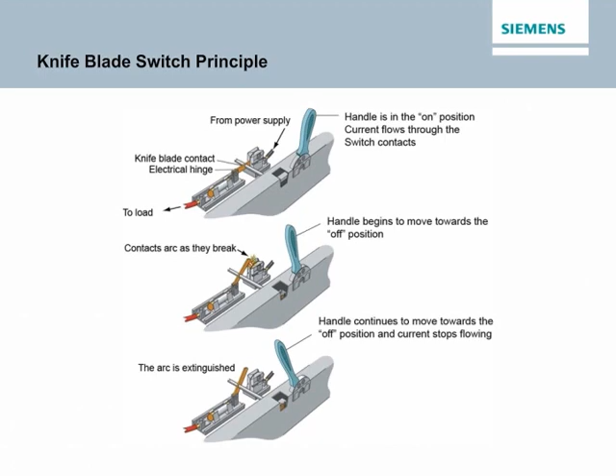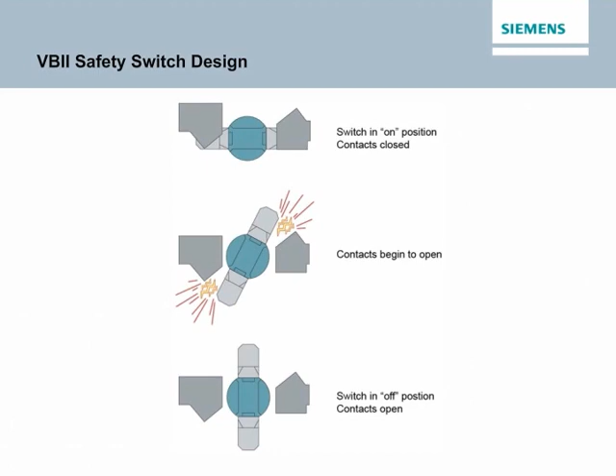Unlike the knife blade switch, the switching action of the Siemens 30 to 200 amp VB2 safety switch breaks the arc in two places. As a result, two smaller arcs are created and heat generation is reduced. The switching speed is also increased, since the breaking distance is effectively doubled. The overall result is enhanced performance and increased longevity. Also, in contrast to the knife blade switch, the VB2 safety switch blades are self-aligning, ensuring positive contact.